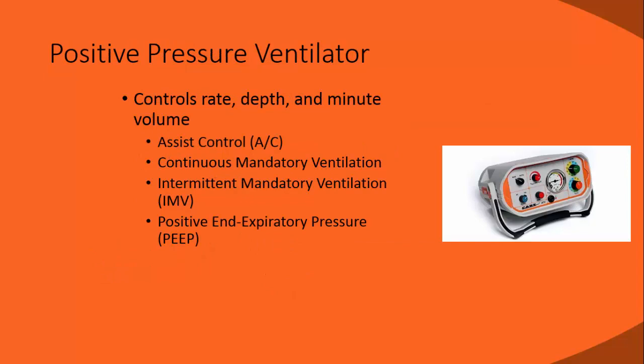Positive pressure ventilators, or automatic transport ventilators, as they're called, have a few different settings and a few different brands. And we're going to look at one specific that you'll see in the paramedic classroom, the Parapac, which is a great device because, like our field hospital devices, this is the care device. Any of the pre-hospital devices that are ventilators don't utilize energy generally, aside from some battery power. But the energy that's required is all just kind of mechanical by these dials instead of push buttons. And then your oxygen connects to this and provides the flow rates that we needed. So there's many different types of ventilators, but some of the common ones that we'll see are going to be our assist control, aka our CMV, continuous mandatory ventilation.